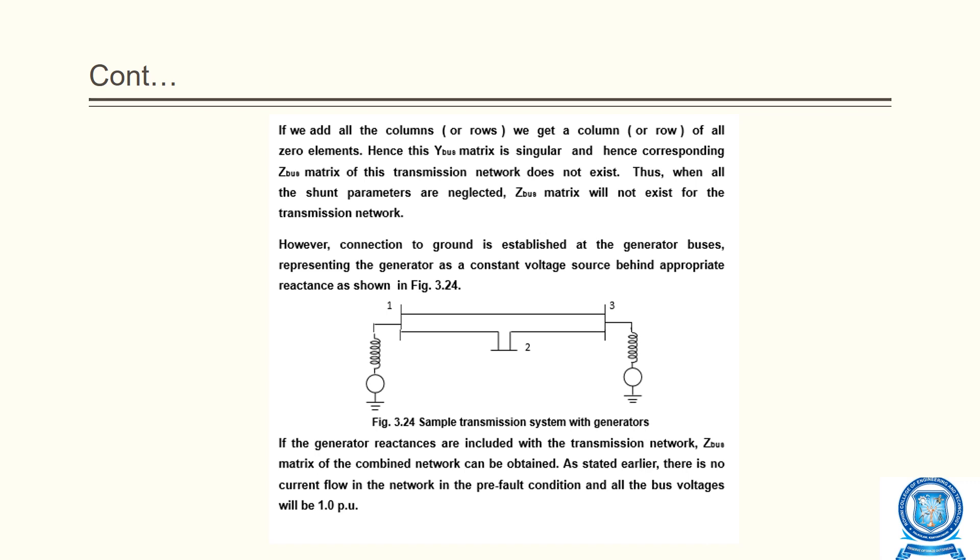However, connection to ground is established at the generator buses, representing the generator as a constant voltage source behind appropriate reactance as shown in the diagram. If the generator reactances are included with the transmission network, the Z-bus matrix of the combined network can be obtained. As stated earlier, there is no current flowing through the network in pre-fault condition and all bus voltages are 1.0 per unit.